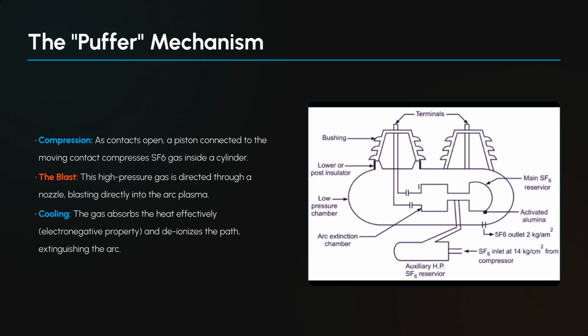The puffer mechanism uses SF6 gas to extinguish the arc. As contacts open, a piston compresses the SF6 gas. This high-pressure gas then blasts directly into the arc plasma. The gas quickly absorbs the heat, extinguishing the arc.